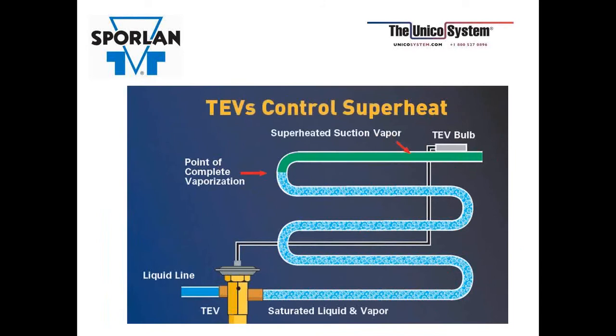When refrigerant is present in both liquid and vapor forms, it is considered a saturated liquid or a saturated vapor. The saturation temperature is the temperature that the fluid is during the phase change from liquid to vapor or from vapor to liquid. Saturation occurs in both the condenser, as it changes state from a vapor to a liquid, and the evaporator, as it changes state from a liquid back to a vapor. At saturation, the liquid has experienced its maximum temperature for that pressure, and the vapor has experienced its minimum temperature for that pressure. However, both liquid and vapor are at the same temperature for a given pressure when saturation occurs. These pressure-temperature relationships are plotted in your PT charts that are referenced every day by you guys. Superheat always refers to a vapor, and subcooling always refers to a liquid below its saturation temperature.